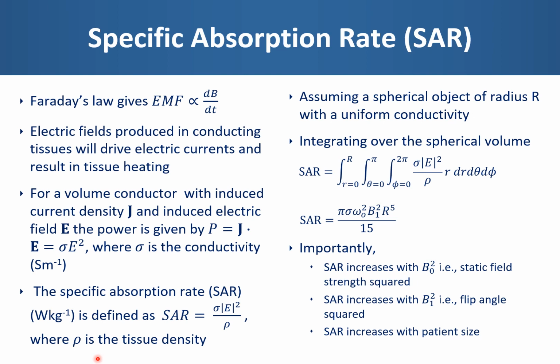The specific absorption rate, or SAR, in watts per kilogram is defined as the conductivity sigma multiplied by the induced electric field squared divided by the tissue density. The SAR for a particular pulse sequence is estimated by the MRI system manufacturer, whilst the limits are defined in an international standard, IEC 60601-2-33. The right-hand side of this slide shows the derivation of an estimate of the power deposition in a spherical object with a uniform conductivity.